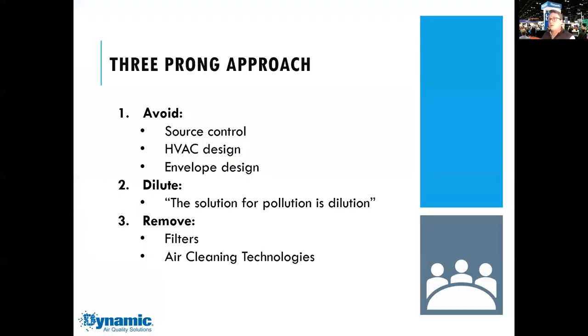Now, from a design standpoint, there's a three-pronged approach. From the side of designers and engineers, the first thing to do is always try to avoid it: source control, HVAC design, envelope design. If you avoid it up front, it helps the IAQ solution immensely. The second solution is dilution, and that's been a common adage in the IAQ world for a number of years: the solution for pollution is dilution.